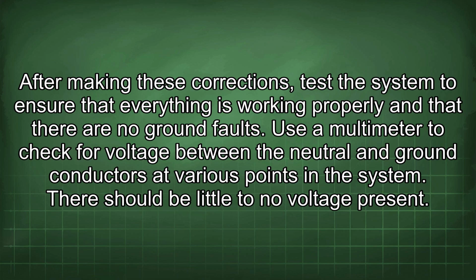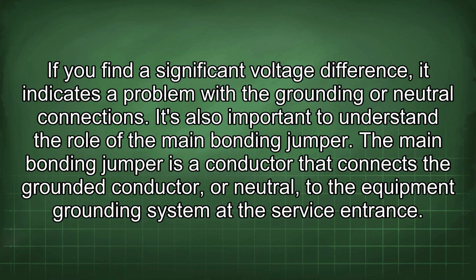After making these corrections, test the system to ensure that everything is working properly and that there are no ground faults. Use a multimeter to check for voltage between the neutral and ground conductors at various points in the system. There should be little to no voltage present. If you find a significant voltage difference, it indicates a problem with the grounding or neutral connections.